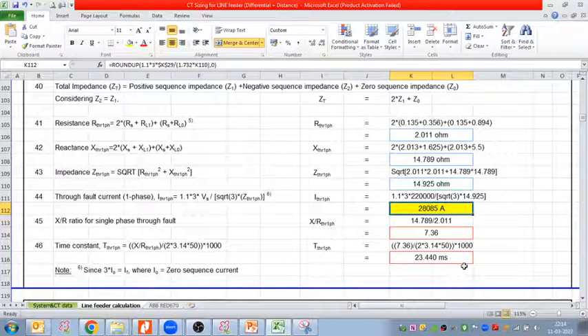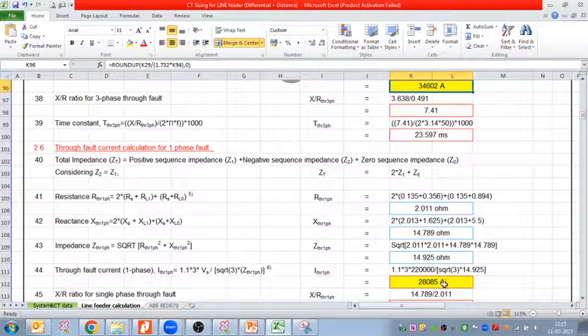So what I wanted to tell you, comparing both cases, is that when you are doing the calculations, if you go with only the three phase fault current, that is also enough and sufficient, right? So here you need to take your three phase fault current value. The single phase fault current, if you want, you can avoid also.